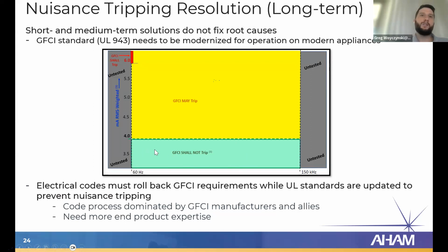We see this green zone expanded. It's not just this skinny little bar at 60 hertz, but the GFCI shall not trip if it's safe at 60 hertz or any other frequency. So if you have a variable speed drive or an LED driver operating in this range, the GFCI shall not trip. And I would expect GFCIs to be updated maybe in the 2028, 2029 timeframe. It's going to be a while for them to update their products and manufacturing lines, but that is being worked on.